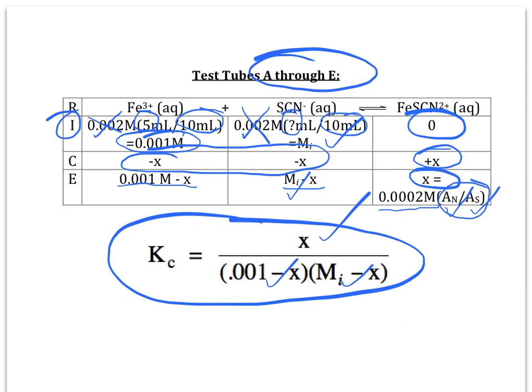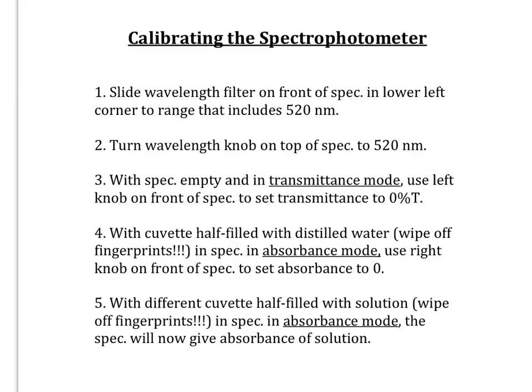Now, let's take just a few minutes to talk about the spectrophotometer to remind you of some key steps as you take spectrophotometer measurements. I know you're all experts from the Beer's Law Lab, but a little reminder can't hurt. Here's the list of things to keep in mind when you're calibrating the spectrophotometer. Remember, there's a wavelength filter on the front of the machine over on the left side. There's two ranges. You want the lower range that includes 520 nanometers. Slide it over so that the range includes 520 nanometers. Then go to the top of the machine and turn the wavelength knob until it reads 520 nanometers.